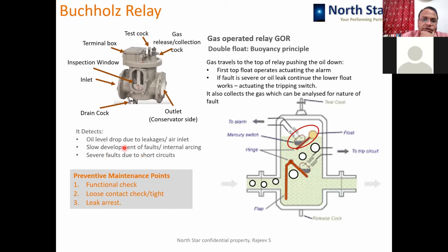If you want to keep it in function, it is very important that you do functional checks. Functional checks means there are two floats or two contacts, and by simulating the gas condition, the operation of these floats has to be checked from time to time. Then leakages: again, it is an oil filled device, so there could be some leakages. Because of leakage, some gas could also get collected when the transformer is on lower load. So leakages have to be arrested and any electrical loose contact has to be tightened.